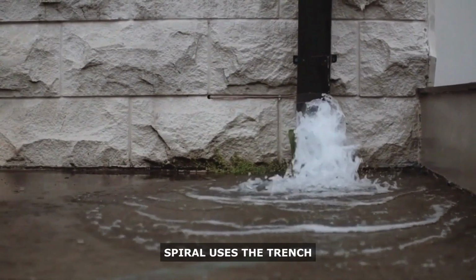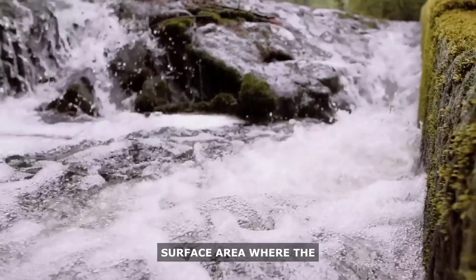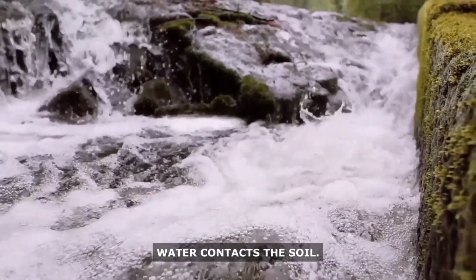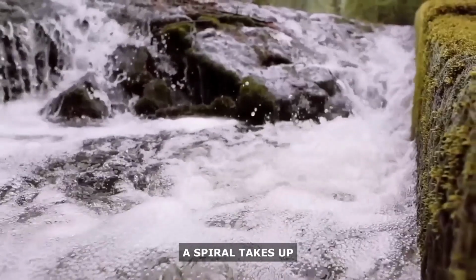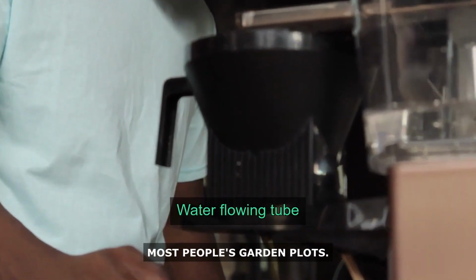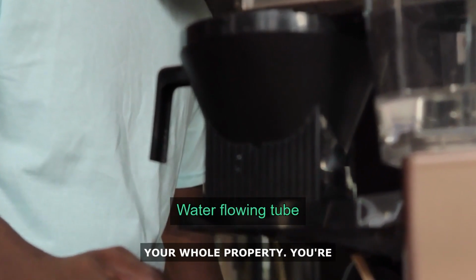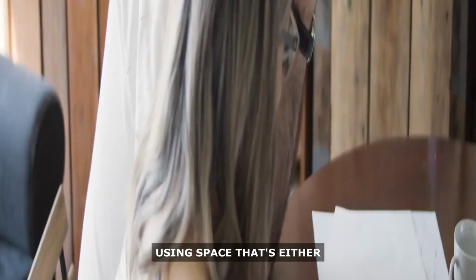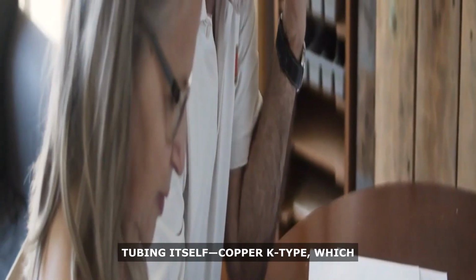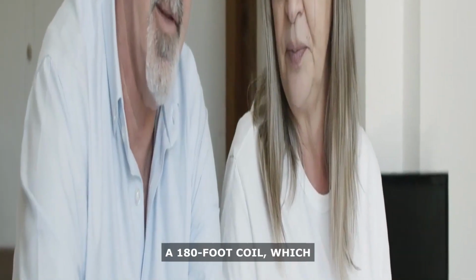The first decision you'll make is the configuration of your coil. Most people build a spiral, because a spiral uses the trench efficiently and maximizes the surface area where the water contacts the soil. A 4-foot deep trench in a spiral takes up maybe 100 square feet of your yard space, smaller than most people's garden plots. You're not tearing up your whole property, you're using space that's either underneath your grass or in a corner that nobody uses anyway.